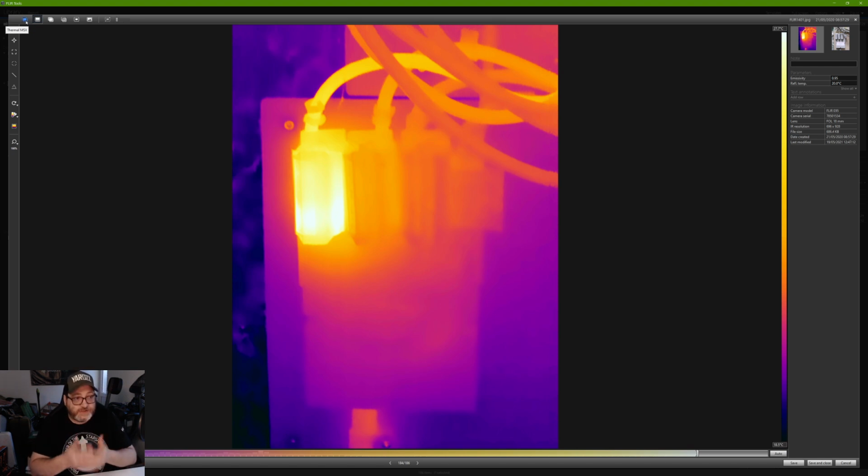Now, thermal MSX is used with all of the FLIR's cameras, and it's just a way that merges some of the technical information of the real-time image underlaid onto the thermal. But you do need to remember that the real-time image and the thermal image are two lenses, and there is a bit of a gap. So depending on your angle and your distance, the MSX and the real-time image may actually be significantly out of alignment. And something that we don't really have here is a way to bring that back.